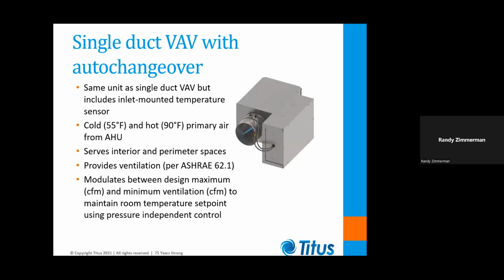Now here's a sequence that's little understood by people, and that's auto changeover. Let's say that we've got VAV boxes in a small tenant space, and that tenant space maybe has a rooftop unit, and that rooftop unit can provide cooling, but also has central heat in it, maybe gas-fired heat. So that would be like a small lease space in an office park or something like that. And if we put VAV boxes inside that suite, then the boxes need to know whether the air handler is in heating or cooling. So that typically involves putting some kind of an inlet mounted temperature sensor on the box, so that the box knows whether the supply air temperature is warmer or cooler than the room temperature that we're trying to control. That allows the box to know whether it should be opening or closing to counter changes in room conditions.